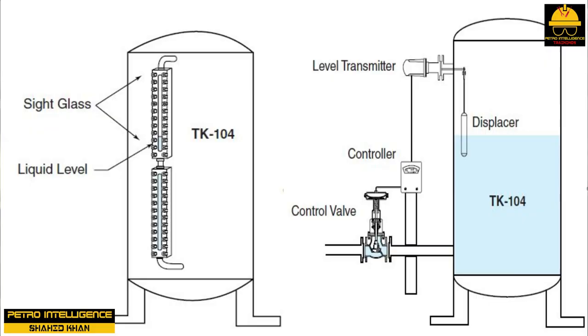Direct level measurement instrumentation is in physical contact with the surface of the fluid and may calculate the product surface level from a specific point of reference. Direct instruments include sight glasses, floats, displacers, and probes. A sight glass is a transparent tube with graduated markings mounted on the side of a tank. In a float and tape device, a float rests on the surface of the fluid and the tape moves up and down depending on the level. Displacers are buoyancy devices or weights that can be linked to a transmitter to control flow.